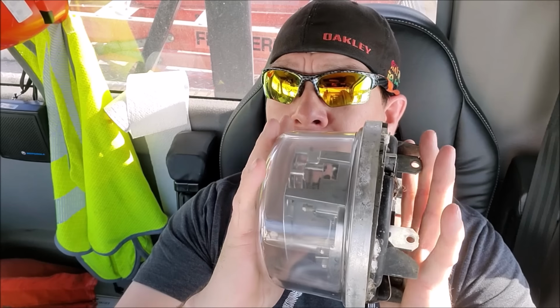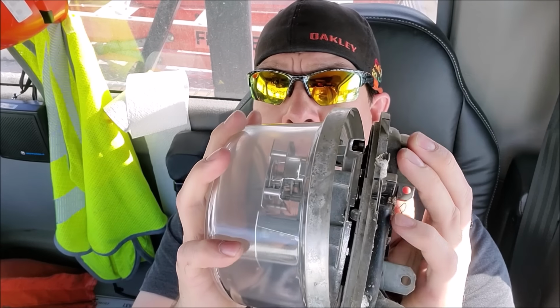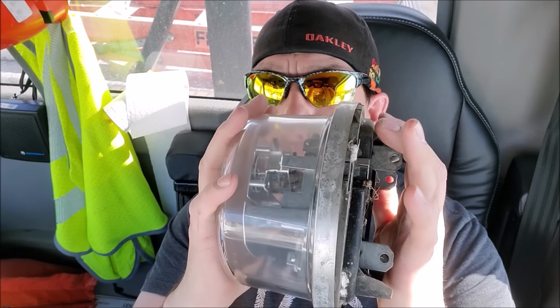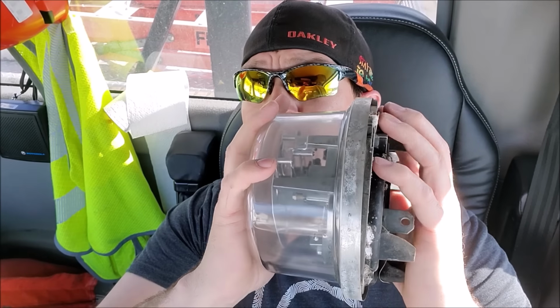All right, guys, that one was easy. You gotta love it when the problem jumps right out at you like that. Sometimes these flickering light calls can be a real pain in the butt to track down the problem. Now, before I go, a couple things here. Our meters are all federally regulated. There's actually a seal that goes between the glass and the meter itself. So if this glass is removed, that seal gets broken.